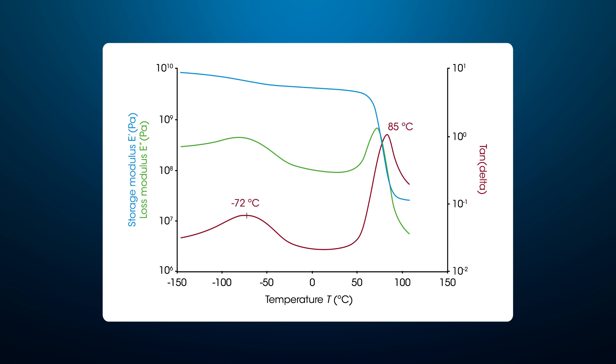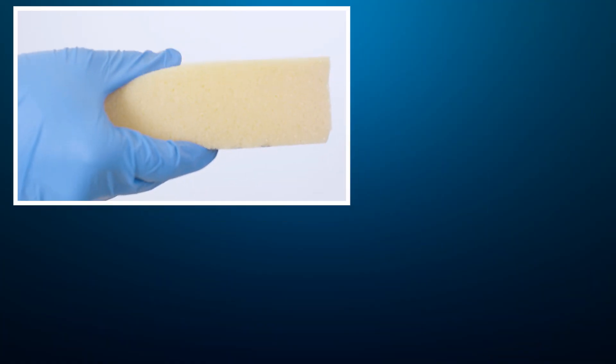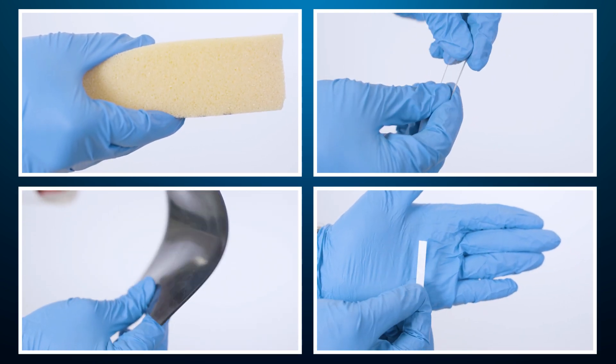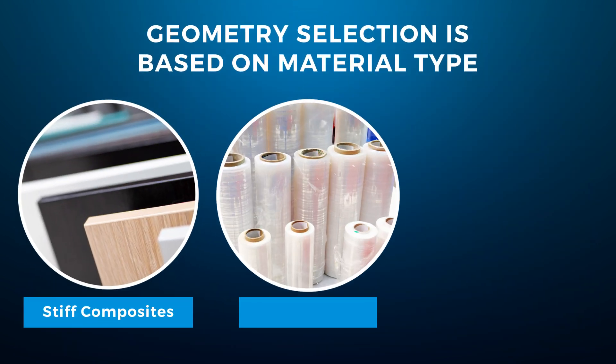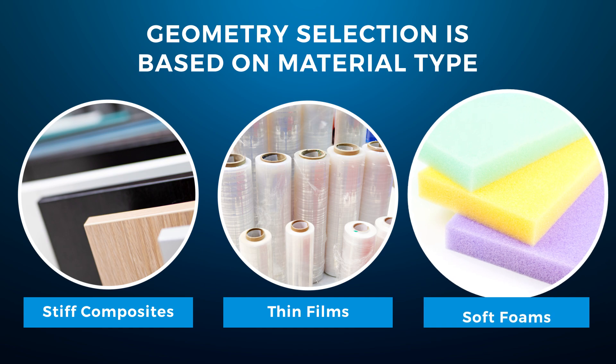Selecting appropriate measurement geometry based on the sample's dimension and stiffness is critical to ensure good and reliable results. Solid samples come in a wide range of materials, differing in their shape and stiffness. Here, we will look at options available for testing solid samples, ranging from stiff composites to soft foams.